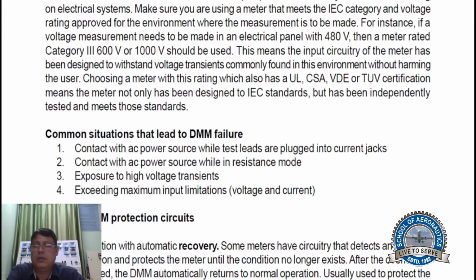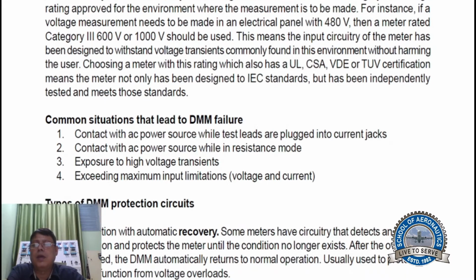Common situations that lead to DMM failure: contact with an AC power source while the test leads are plugged into the current jacks; contact with an AC power source while in resistance mode; and exposure to high voltage transients exceeding the maximum input limitations of voltage and current.